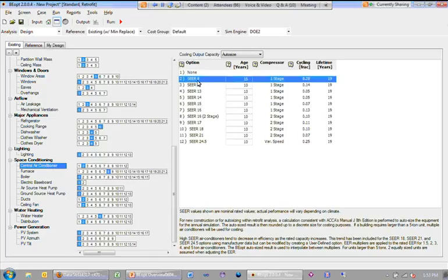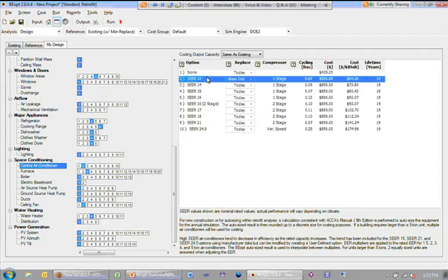So it would be unrealistic, if you're looking at putting in wall insulation, to say, how does my new wall insulation fare in the context of a SEER 8 air conditioner, when you know that SEER 8 air conditioner is not going to last for more than a few years on average, and that when it wears out, you have to put in at least a SEER 13. So BEopt is trying to have realistic retrofit scenarios over time such that your energy savings reflects that situation.